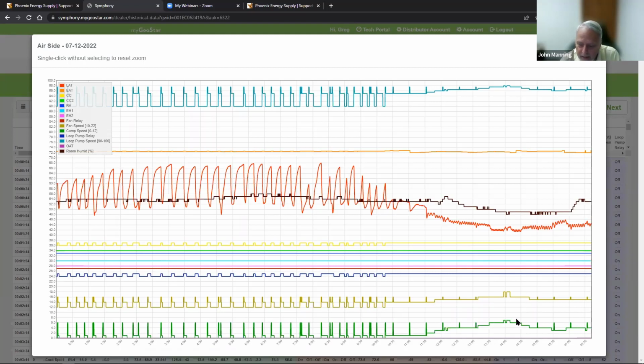But as we got into the warmer part of the day, we can see the compressor ramped up to speed 6 and occasionally went to speed 7. So we can see how it operated. We can get the supply air temperatures. And under these higher speeds, we were able to, one, maintain a constant return air temperature, but deliver cooler air to the space. It's a powerful tool.